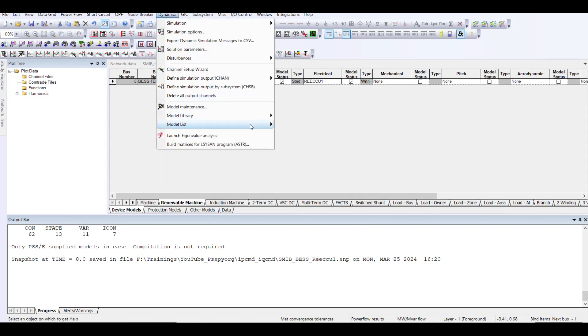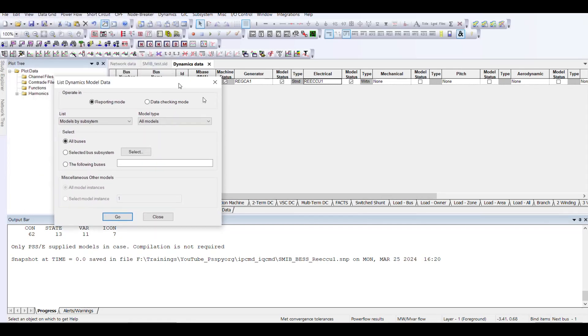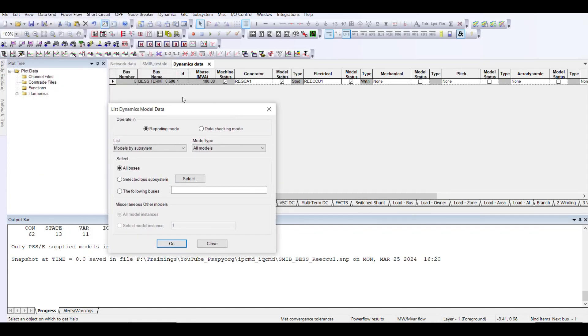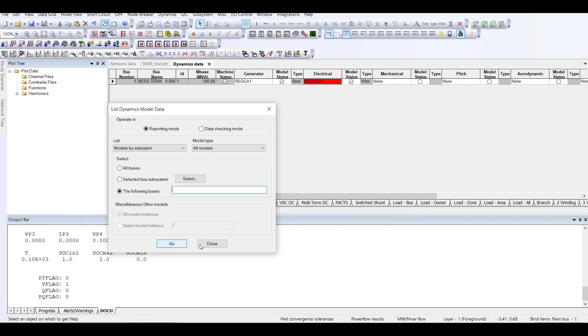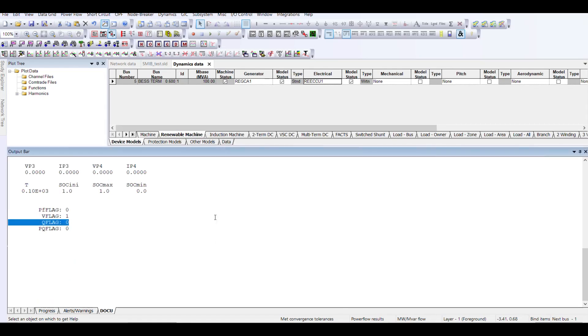To get these values, go to PSSE, then from Dynamics go to DOCU. Within DOCU, I would like to check all the models for bus number 5. Once I do this and press Go, all the models connected to bus number 5 will appear.